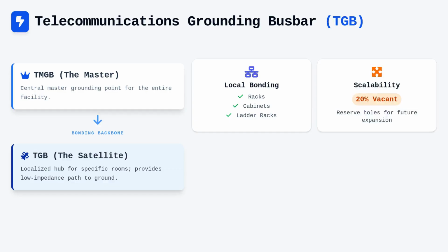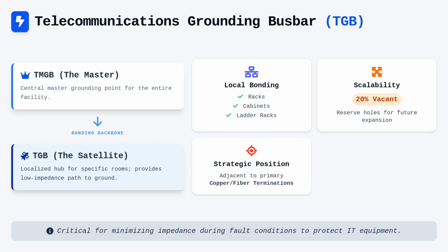When sizing these components, you should reflect on the total number of telecommunications equipment connections expected in the future, as bus bars are difficult to upgrade once the cabling infrastructure is fully populated. It is common practice to leave 20% of the holes on the TGB vacant to accommodate future expansion, preventing the need for disruptive retrofitting later. Placing the TGB adjacent to the primary copper or fiber backbone terminations creates a short, direct path, which is critical for minimizing impedance during fault conditions. Keep in mind that TGBs, like the TMGB, must be clearly identified and labeled to comply with safety standards and facilitate troubleshooting for maintenance personnel.